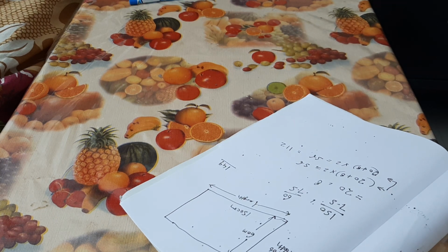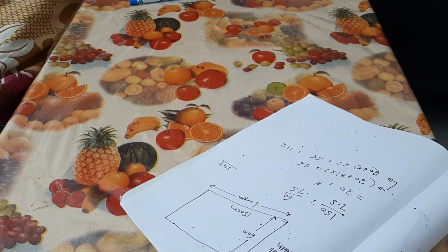What we have to do is, since we have calculated 149 tubes, this is the economic size that will help the transformer to cool down, and it does not result in any short circuit or anything due to the heat and transformer bursting. Hence we have to take into consideration all the economics. The number of tubes should be around this figure or more than it. It should not be less than it, because we have to maintain the temperature and thermal considerations. So 112 happens to be a little small number.